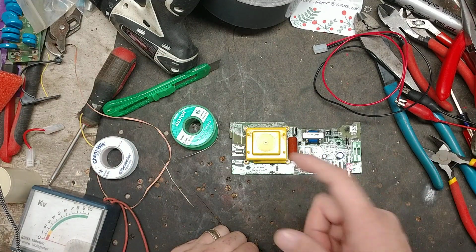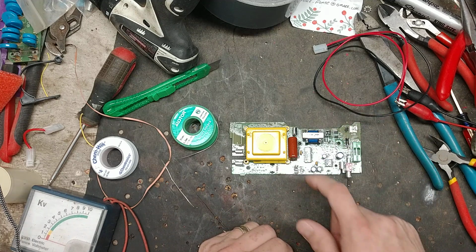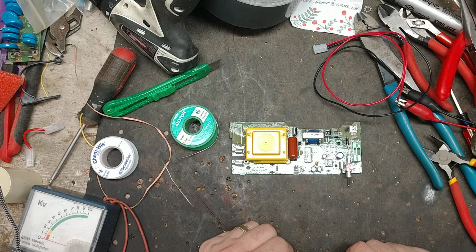There's a few things that cause it not to click, not to discharge. And the capacitors hardly ever go bad. So we only change these out if they're split and cracked and broken, which is pretty rare, or if the person wants to change it to the next size bigger, then we'll do that for them.